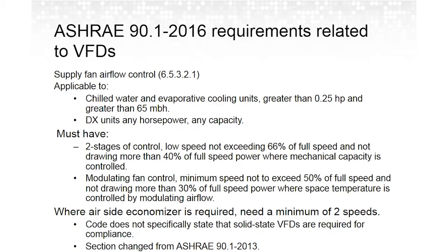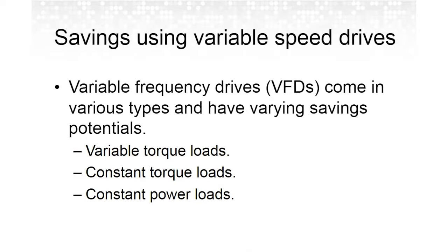And in most cases, the various different methodologies that you might use for air systems, like inlet guide vanes or vane axial fans with variable pitch blades, things along those lines, typically will not meet the minimum requirements for efficiency under part load conditions. So as a result, use of VFDs becomes de facto in most of those types of situations. And I will hand it off to Ken now.